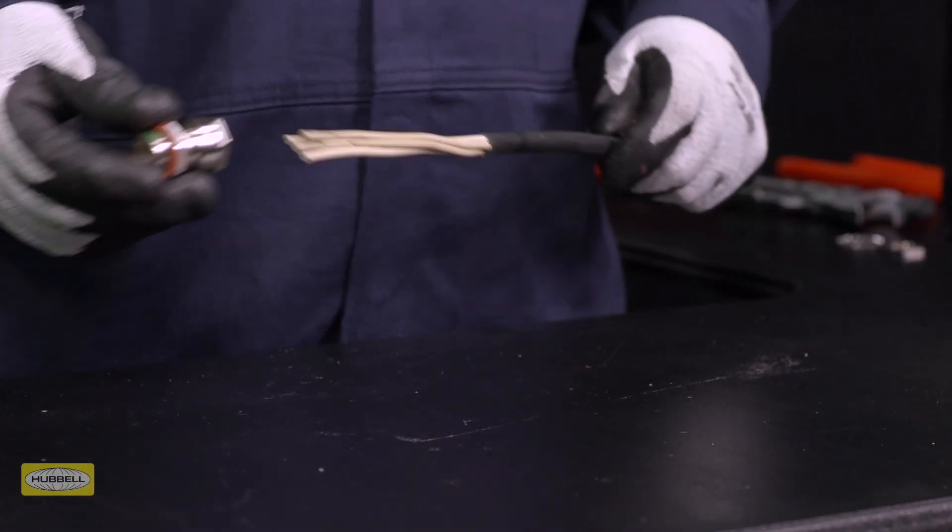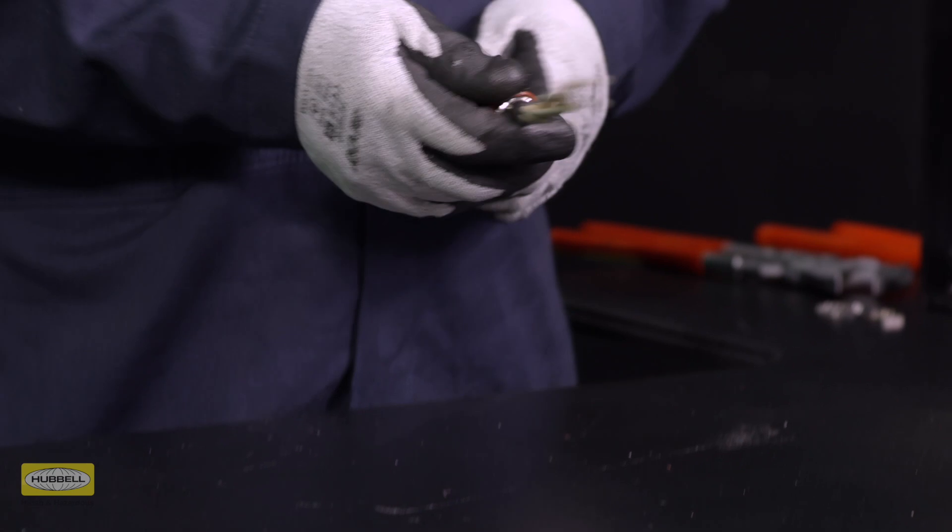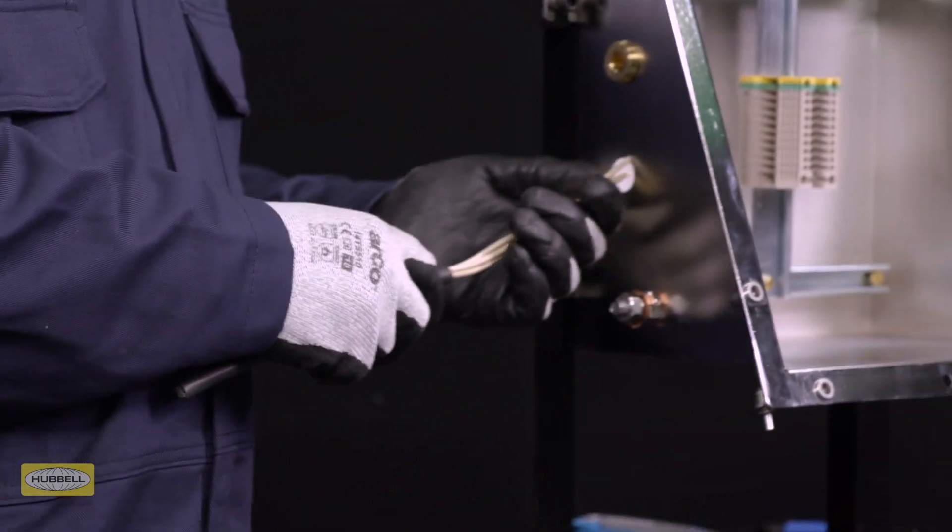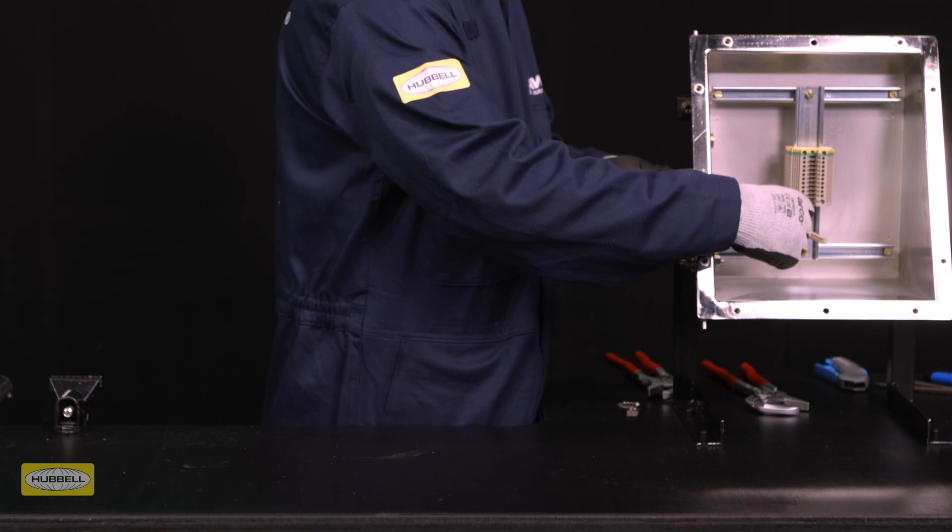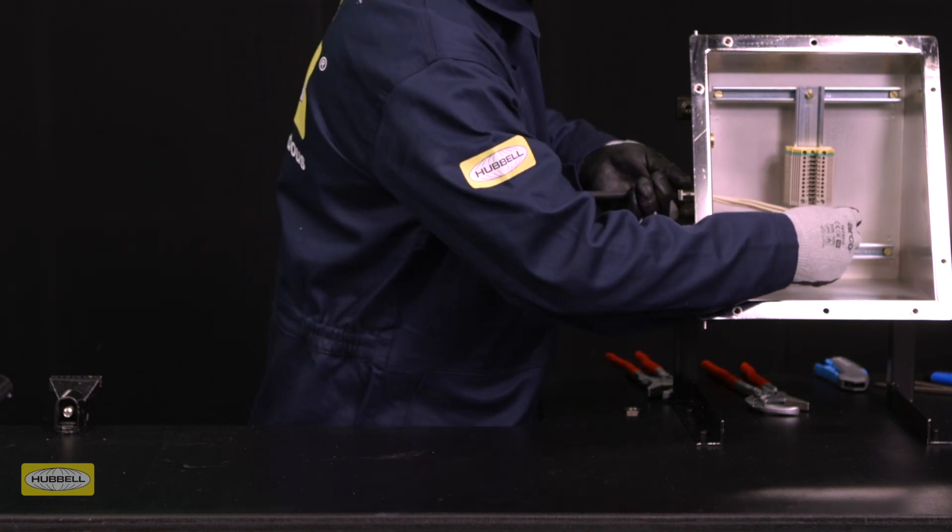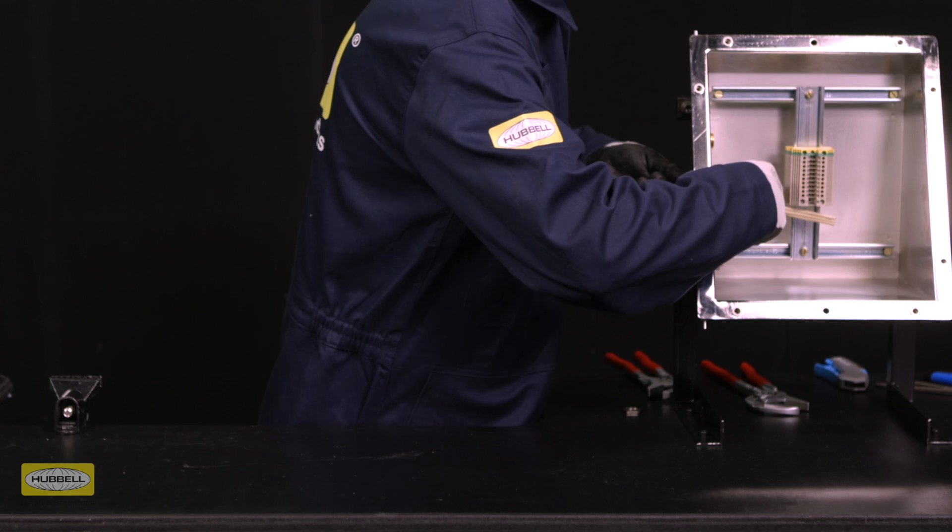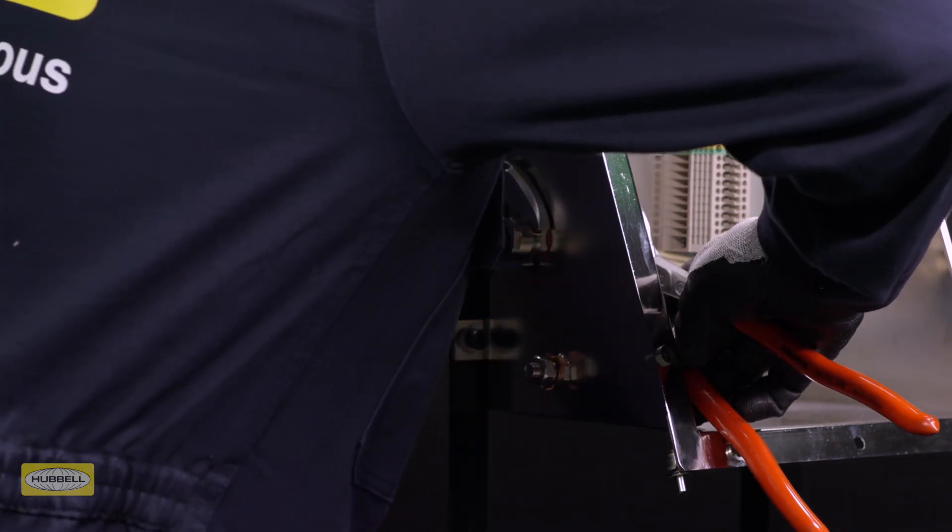Pass the cable through the cable gland. Please note, if the equipment has a threaded entry, it may be advisable to screw the cable gland into the equipment to prevent twisting of the cable. The method of installation may vary depending on the enclosure type.